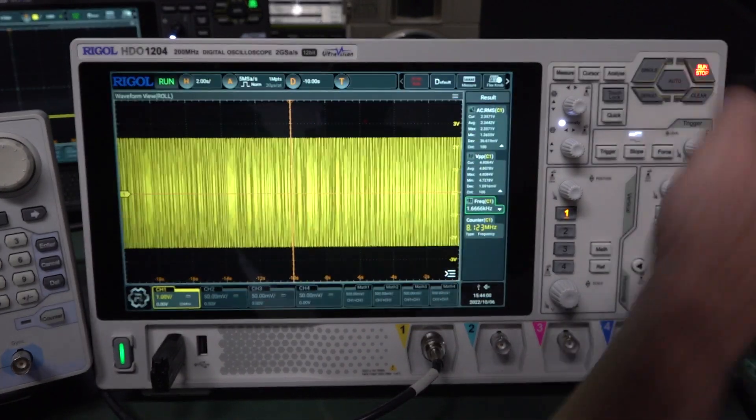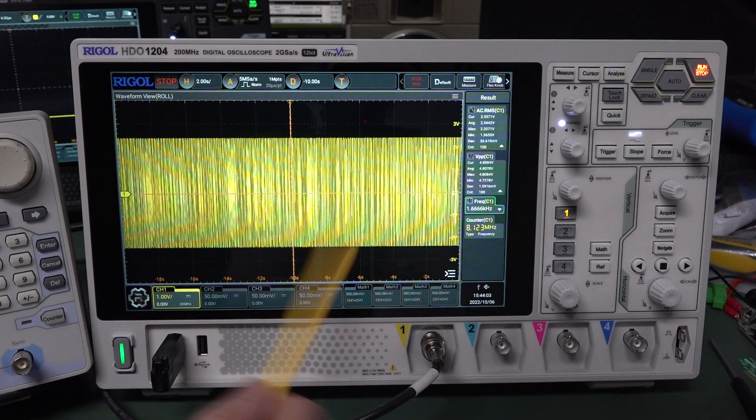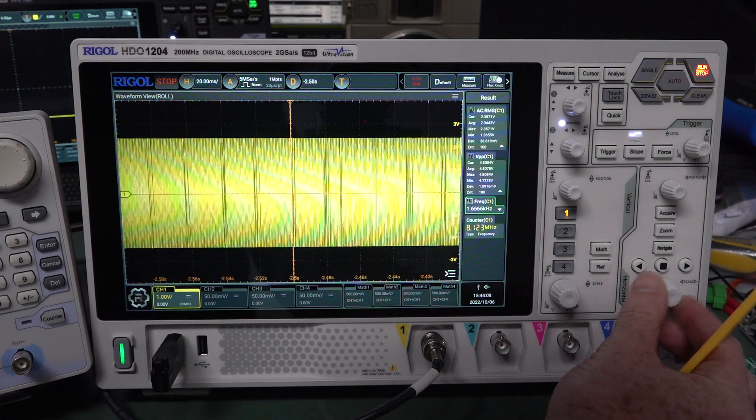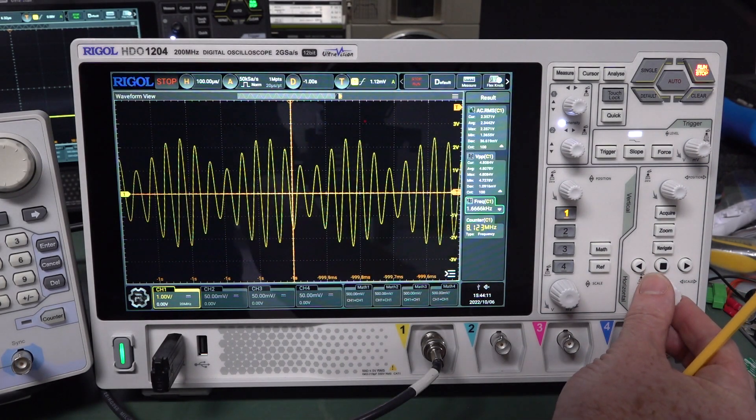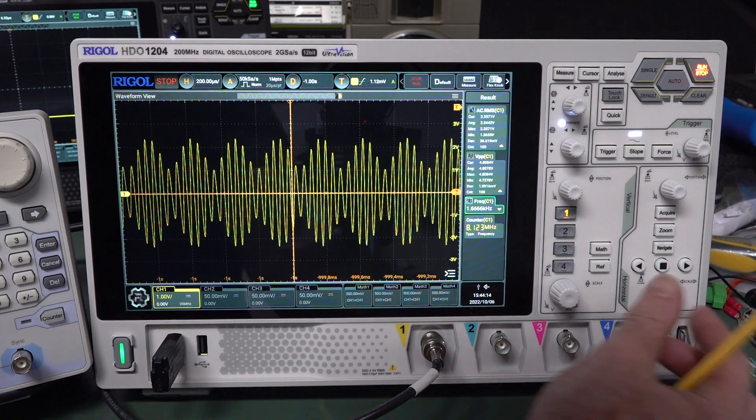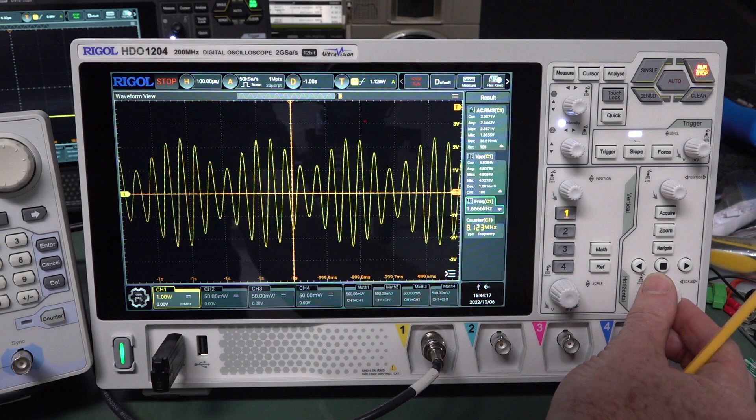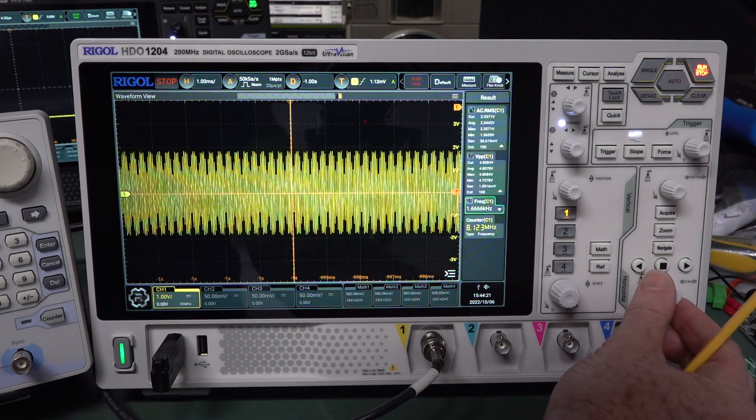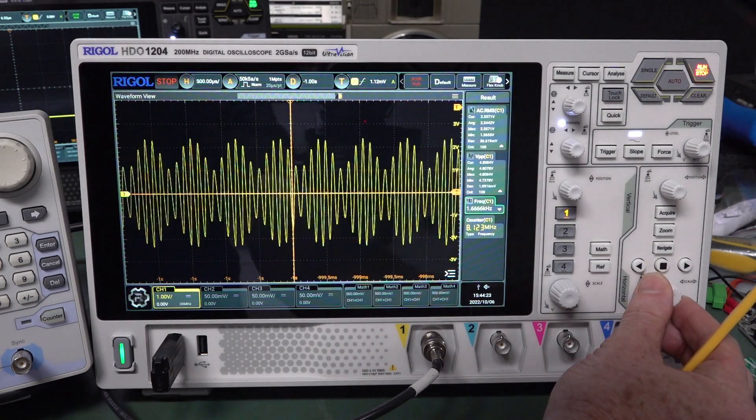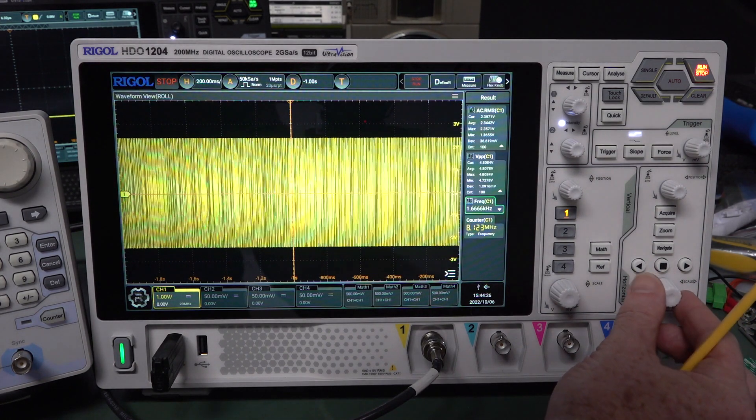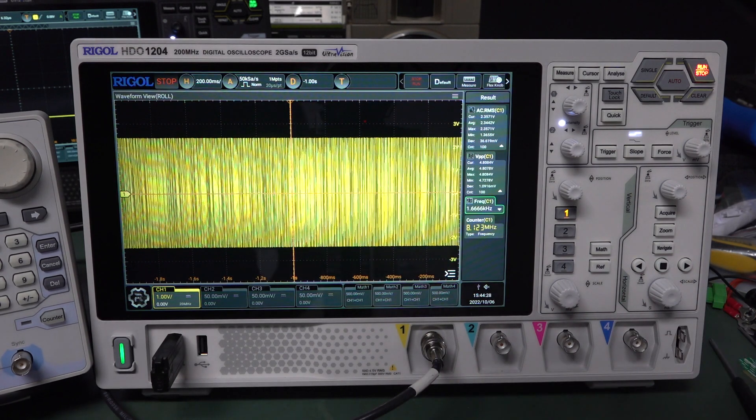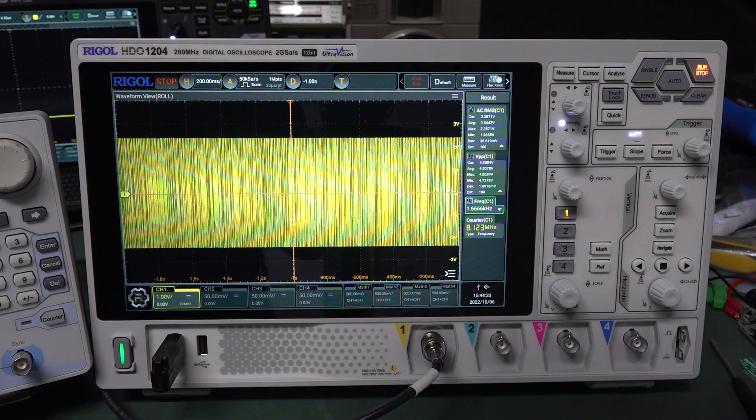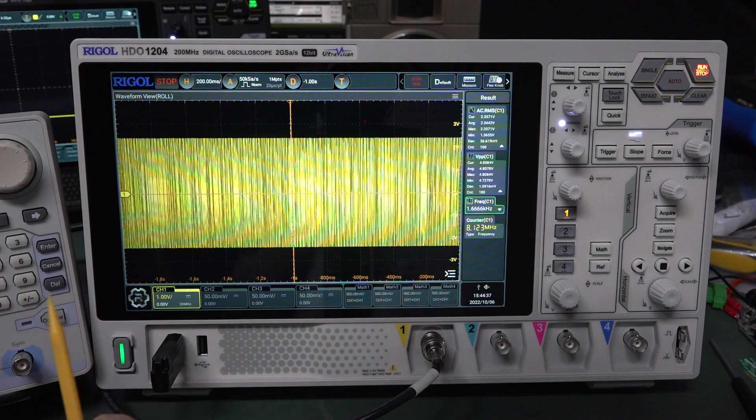So if we actually stop that, and stop is different, by the way. Look, it actually displays, what it's displaying on the screen is actually quite significantly different. We can actually go back, right? Way! There we go. There's your problem, right? There is no modulation on this signal, but it's showing it because it's an oddball. And you can go into the math behind it, and you can go into the sample theory, and you can go into the whole works, right? Because this does not have an anti-aliasing hardware filter in it. It's not doing that based on the sample rate, whereas I think the Keysight does actually do that.